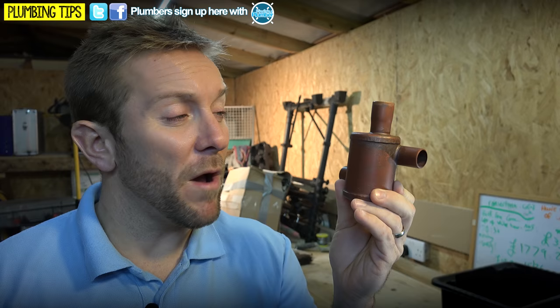So, what these do is basically de-aerate any air out of the system water of a heating system. Now, it's very important to not have any air at all in a heating system, or at least to a complete minimum, because it affects how the heating system runs. You can get airlocks, problems with flow. It can upset radiators, pumps, boilers. It's just bad news. So, we don't want it in there. So, used in conjunction with a decent inhibitor in the heating system, which is going to stop you from creating air in the first place, we're going to get one of these as well and install that on the system to make sure that any air that's in the heating system can leave it nice and easily.